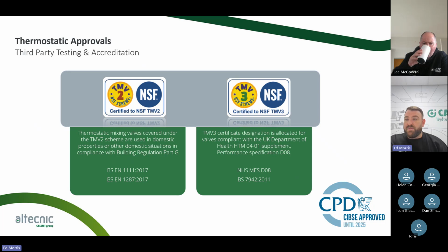It ensures that you can work to both high and low pressures. TMV3 is solely based for healthcare. BS 7942 is the British standard that we test and manufacture to for that, but it's also driven by HTM 04-01 and D08. So it's driven by healthcare.